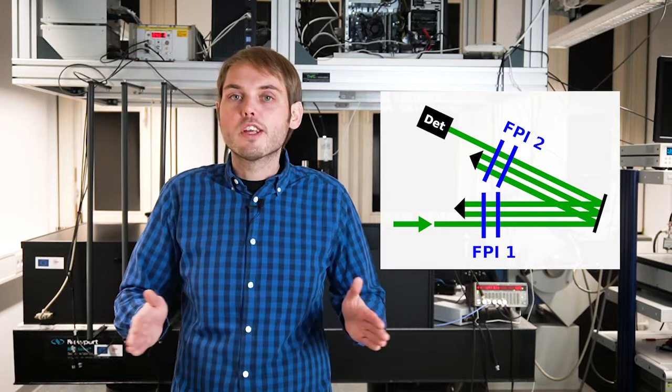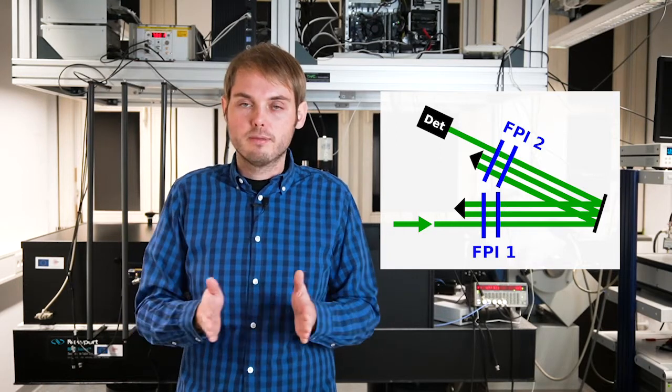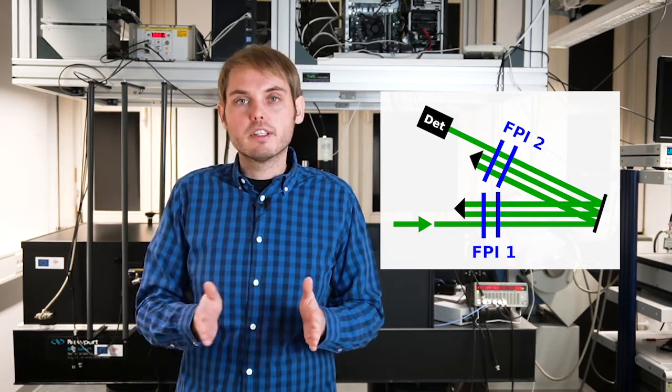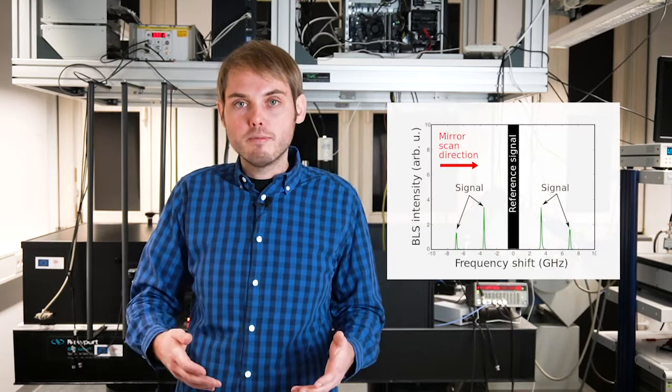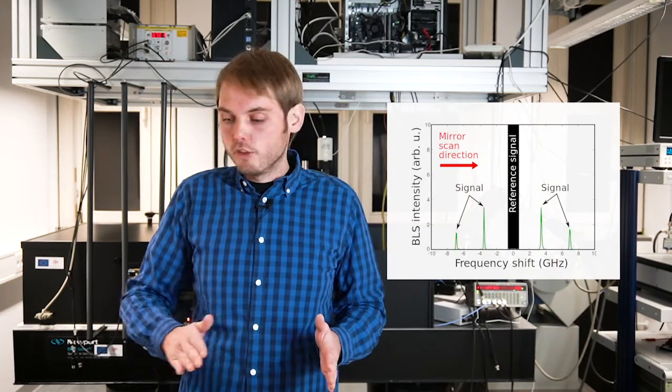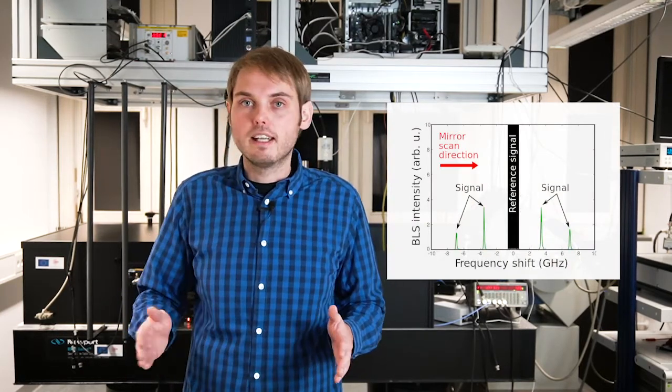And it is not only the low scattering cross-section, but also the working principle of the interferometer itself causing these rather long acquisition times. As I mentioned before, inside there are two pairs of Fabry-Perot interferometers which are being scanned all the time, which is required for the stabilization process. So the distance of the mirrors is varied all the time. And only at a certain distance, your actual signal is being transmitted. And the rest of the scanning motion is basically dead time.